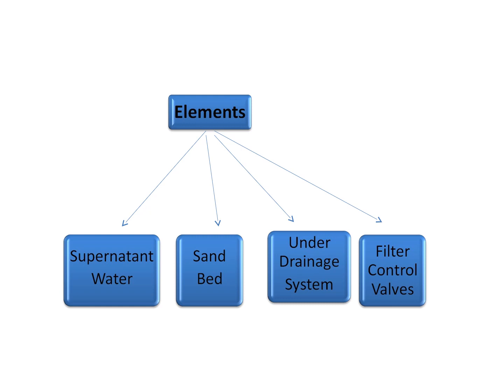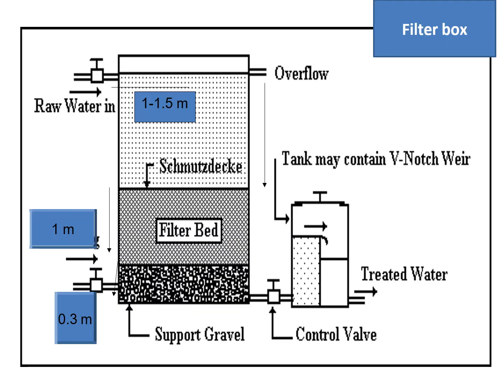Supernatant water is the water that is stored above the sand bed. As the name suggests, water stored above a particular surface is called supernatant water. Below this water is the sand bed, and under the sand bed is the drainage system which controls the outflow of water after purification. To control this outflow there are filter control valves. A slow sand filter consists of these four elements.